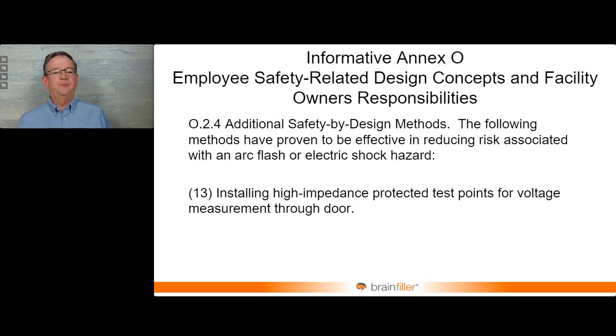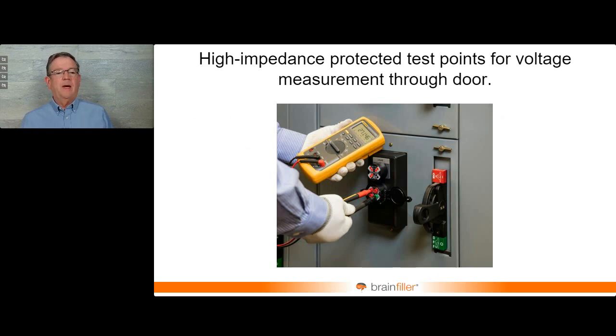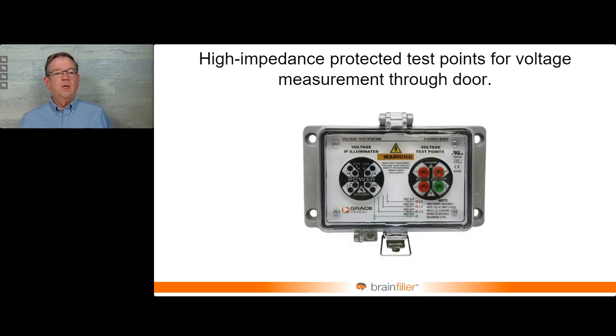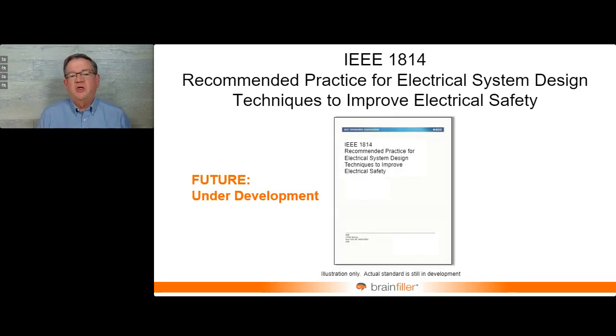Informative Annex O, which is about design, safety-related design concepts. There was a new addition here about high impedance protected test points, where you can measure the voltage through the door, try to minimize your exposure to the hazard. So verify voltage before you open the door. Looks like this.